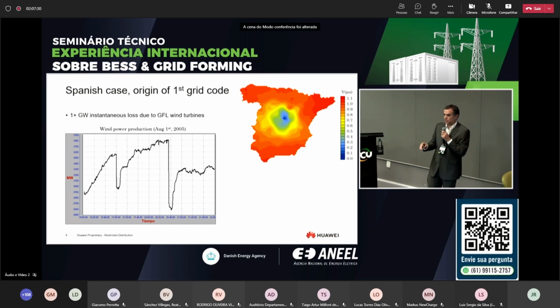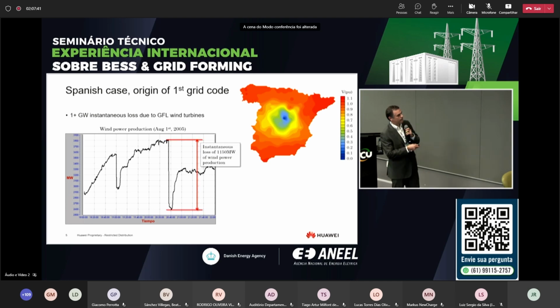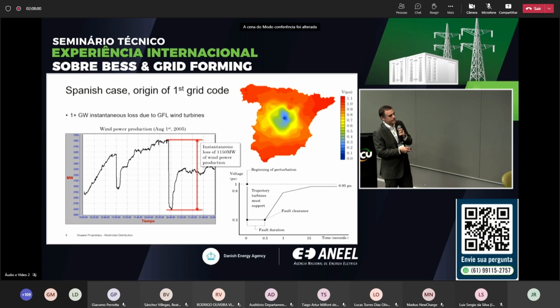In one event, you will lose a lot of power synchronously, and this is a big problem — synchronized events in the grid lead to very big problems. For example, there was an energization of a transformer in Spain at some point, and in 2005 we lost more than 1 gigawatt of production. Then the system operator in Spain said, no, this is not affordable, we need to do something — and they created the first grid code.